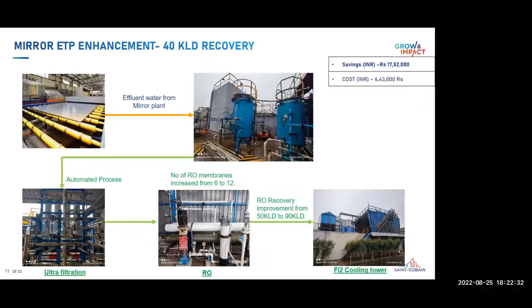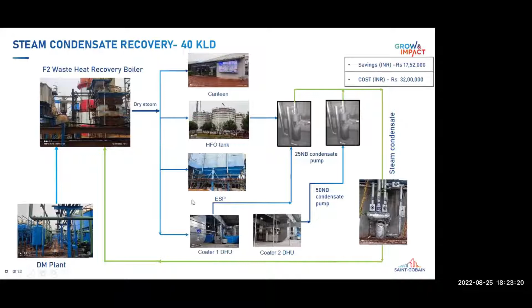Next slide: this is steam condensate recovery. The waste heat from the float two line is used to fulfill our steam requirements at various locations like the canteen, HFO tank, ESP, and coater DHUs. The water we use for waste heat recovery is DM water. Earlier, we did not have any condensate recovery system for the coater 1 and 2 DHUs. We installed a condensate pump, a pressurized power pack pump, after laying the pipelines. The water collected through this condensate pump is transferred and recovered back to our boiler, and thereby we have saved around 40 KL of water. The total cost of the project is around 32 lakhs, and the savings is around 17.5 lakhs per annum.